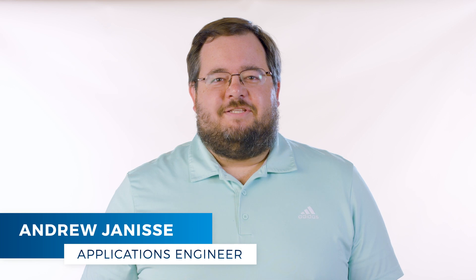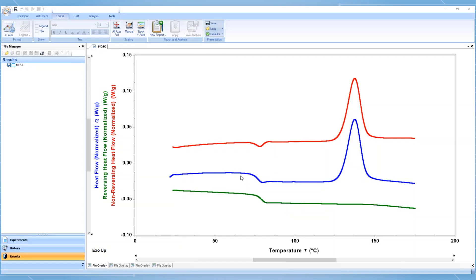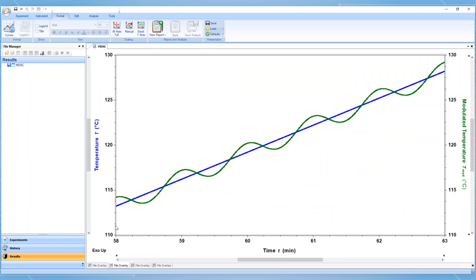Hello and welcome to another TA Tech Tip. In this Tech Tip, we will give a general overview of the parameters you need to select when running a Modulated Differential Scanning Calorimetry experiment, also known as MDSC. In MDSC, the total heat flow, which is recorded in a traditional DSC, can be separated into two parts based on the response of the system to a changing heating rate. This is achieved by superimposing a sinusoidal heating rate, or temperature modulation, on a linear heating rate.